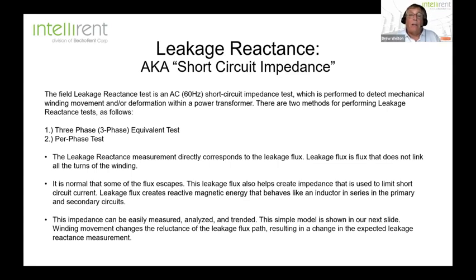Now, there's typically two parts to this test. One is a three-phase equivalent where we're going to measure the impedance of the transformer on all three phases and calculate what that impedance is. And if that impedance is greater than 3% off what's stamped on the nameplate, we have a problem. But then we're also going to do a per phase test. We're going to measure the impedance of each phase independently and compare that with each of the other phases to make sure they're within 2%.